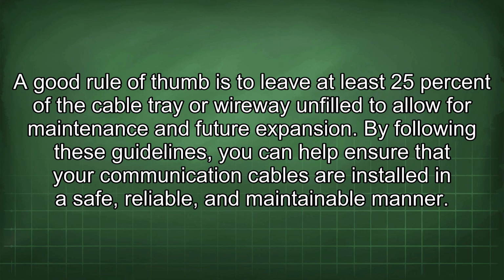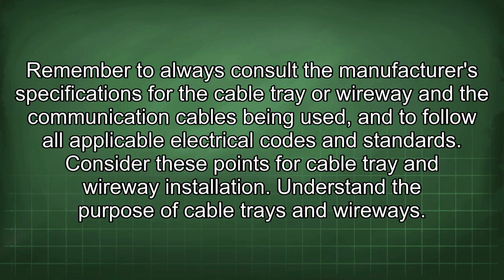By following these guidelines, you can help ensure that your communication cables are installed in a safe, reliable, and maintainable manner. Remember to always consult the manufacturer's specifications for the cable tray or wireway and the communication cables being used, and to follow all applicable electrical codes and standards. Consider these points for cable tray and wireway installation.